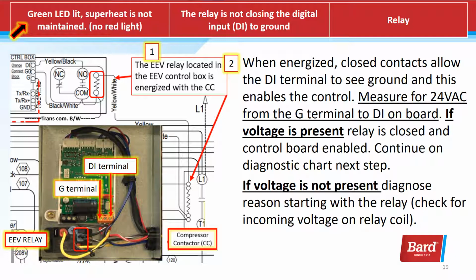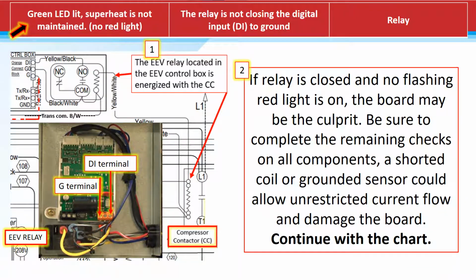If we measure between G and digital input, or DI, G and DI, and the relay is closed, we will get 24 volts. If we don't get 24 volts there, then we need to check the relay and find out why it's not closing. If voltage is present and the relay is closed, then the control board is enabled and we need to continue on to the next step. If the relay is closed and there's no flashing light, the board may be the culprit, but we need to complete our checks to be sure.